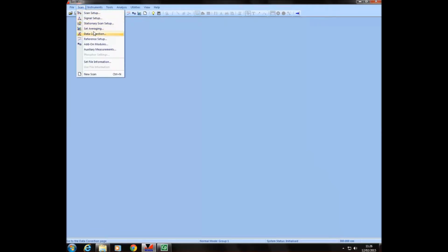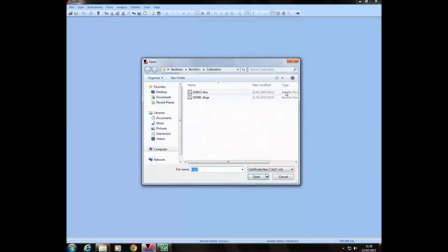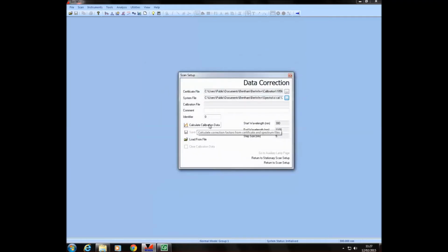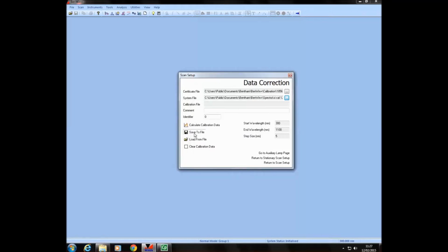In order to apply data correction to calibrate the system, we should go to Scan, Data Correction. The certificate file is the calibrated data in amps per watt of the device that we're using to calibrate the system with, and it is this silicon photodiode with the same serial number. The system file is how we have measured our system with this detector, i.e. the file we have just saved. We can hit Calculate Calibration Data to generate the calibration factors. Data correction is not selected. Do you wish to select now? Yes, we do. And save to file, and we can save it as the SI calibration and perhaps today's date.